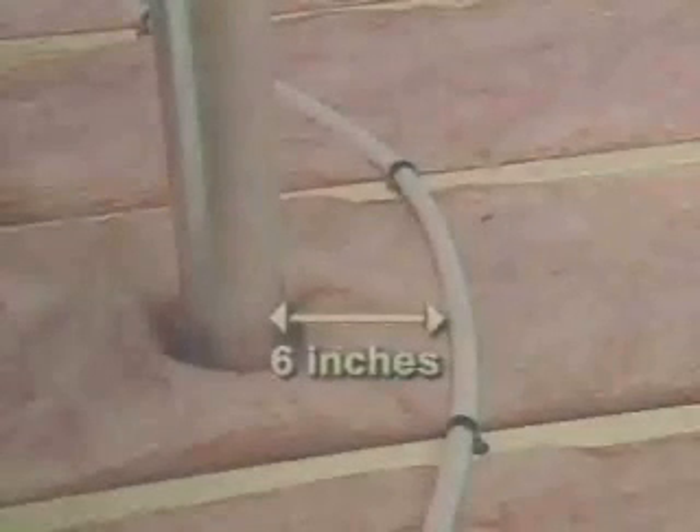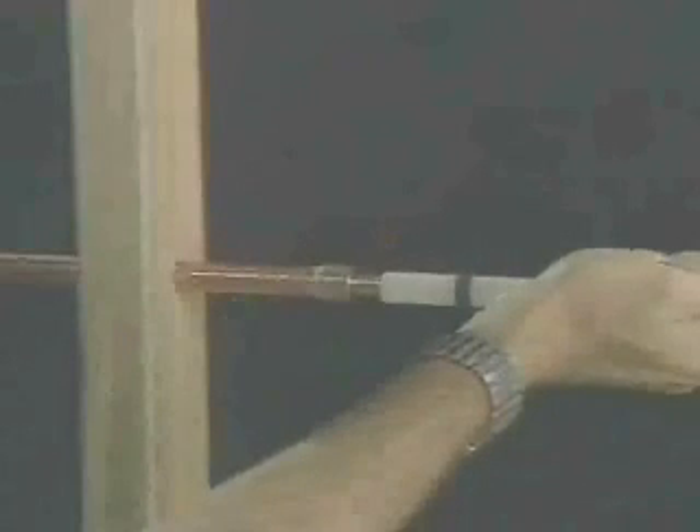Also, don't install cross-linked polyethylene tube within 12 inches of a recessed light fixture. Finally, when making sweat and insert transitions to copper, always make the sweat connection first and let the metal cool down before making the crimp connection to Zurn PEX.